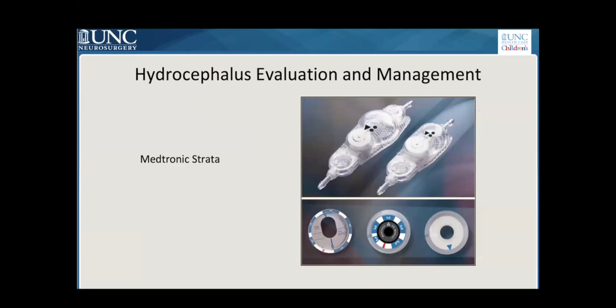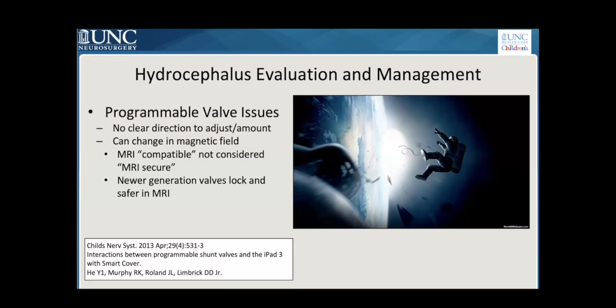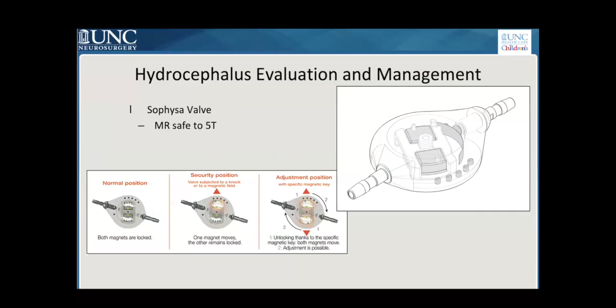These valves, however, have their own issues. So it's really unclear how much to adjust these when somebody comes in. If you have a child who you put a shunt in and now maybe they are saying they've got headaches, well, do they have high pressure, low pressure? So adjusting is a little bit of a best guess game. They also, at least some of the valve designs, can change in a magnetic field. And of course, we try to get MRIs when we're following up with hydrocephalus. More new generation valves actually can lock and so are much safer for MRI, especially if you've got kids getting MRIs that are not at the children's hospital or not near a pediatric neurosurgeon or office that can check the valve after the MRI.